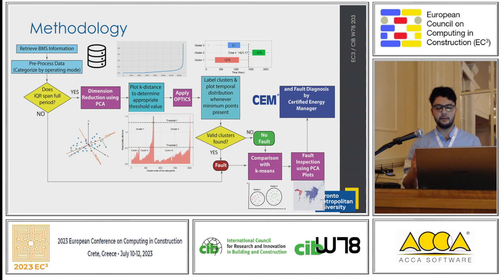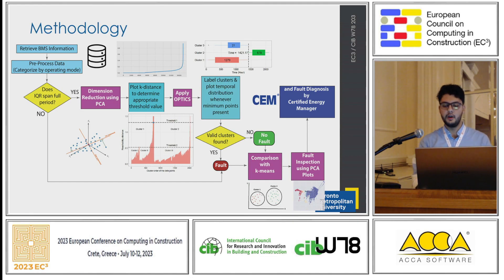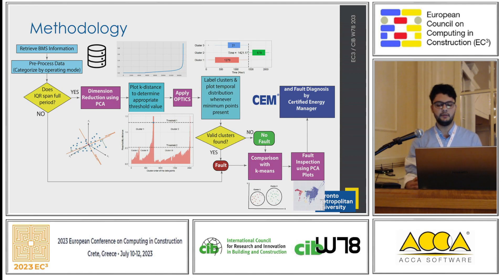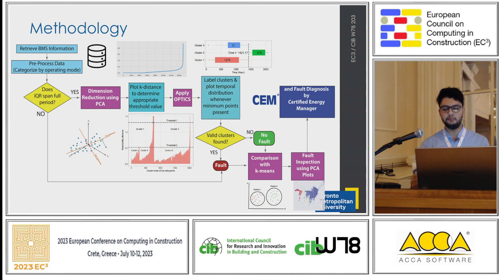This range represents the most concentrated observations. Following this, we used PCA to reduce the dimensions of the data, because irrelevant dimensions may prevent the discovery of real clusters. Once data preprocessing is completed, cluster analysis based on the OPTICS algorithm is then used for data analysis. With OPTICS, some observations will be grouped into different clusters, and the rest of the data in less dense areas will be grouped into one cluster and labeled as cluster zero, which is considered noise and neglected in later stages of fault detection.